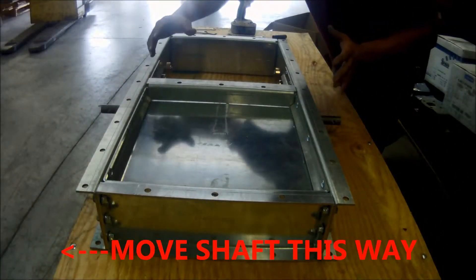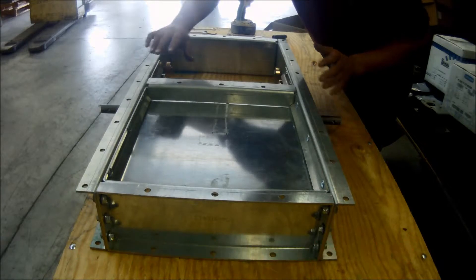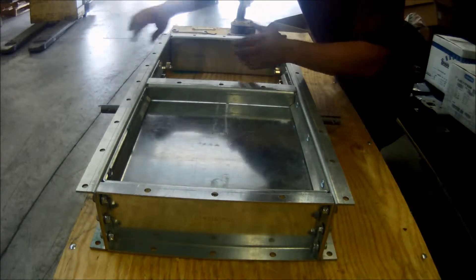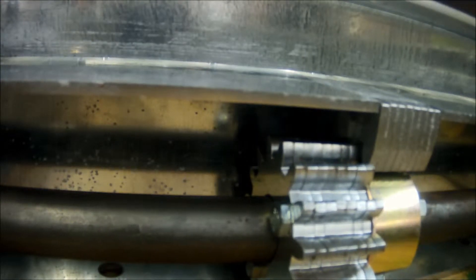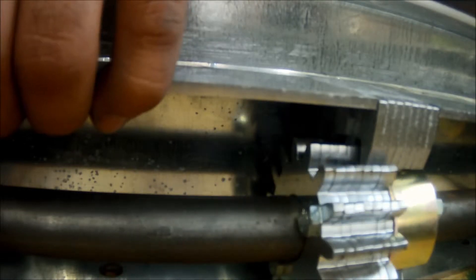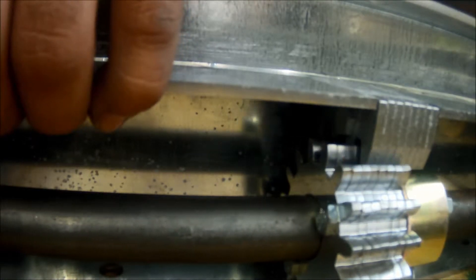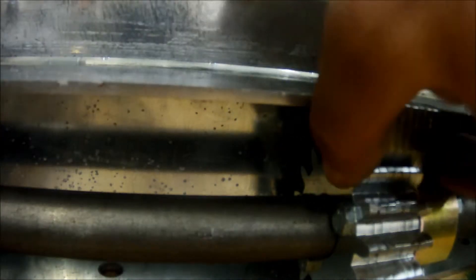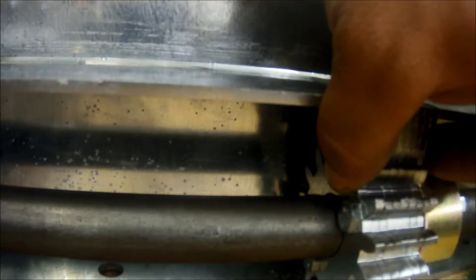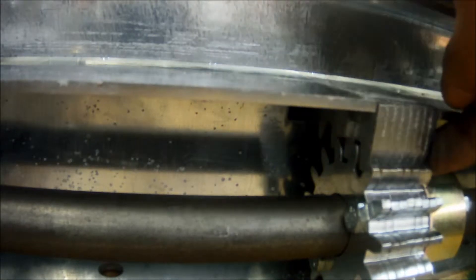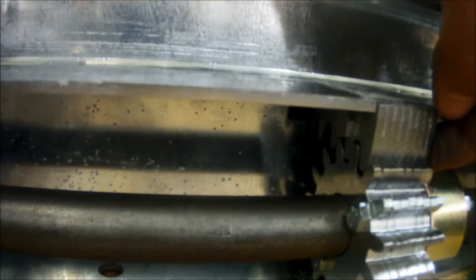The next step would be to move the shaft. We're going to move it in this direction by using a block of wood and a hammer. Once the gear gets close to the rack, you can then use your hands and fingers to align the gears to mesh properly. Be careful that you do not pinch your fingers in this process. Be sure that the gear and the rack are perfectly flush on either side.